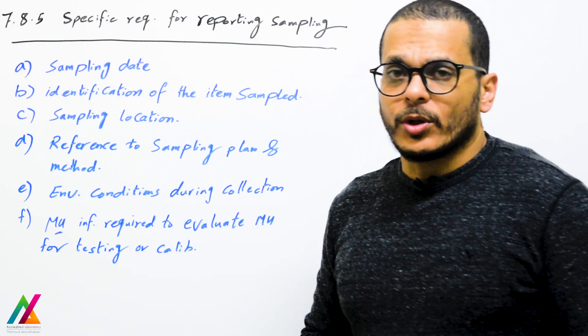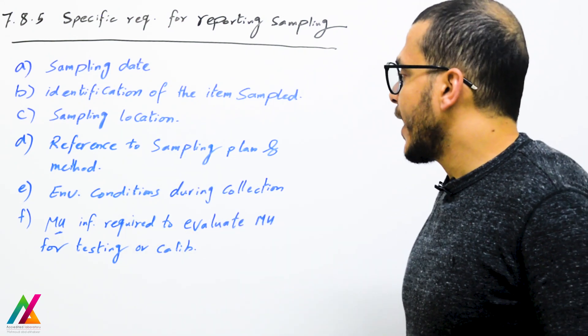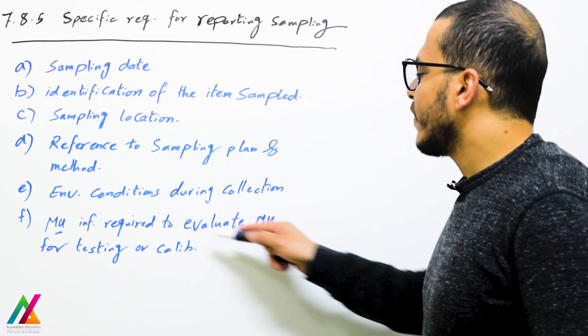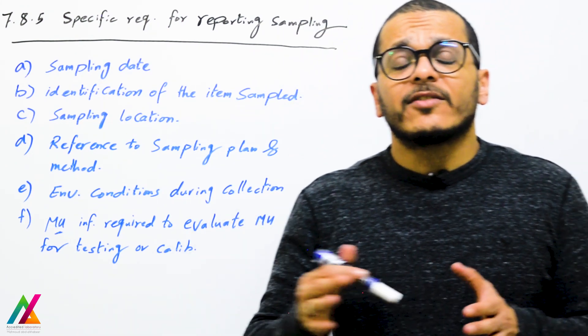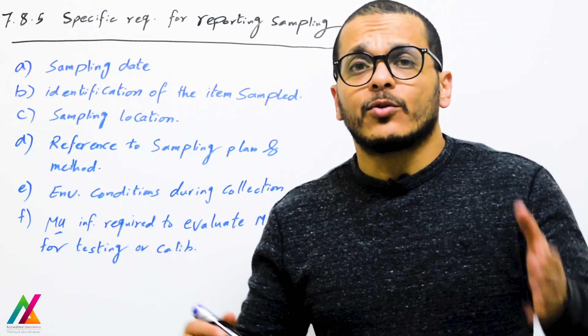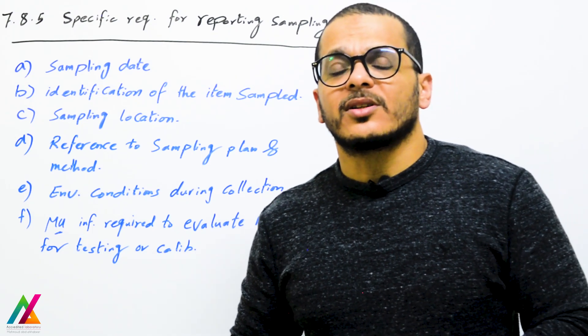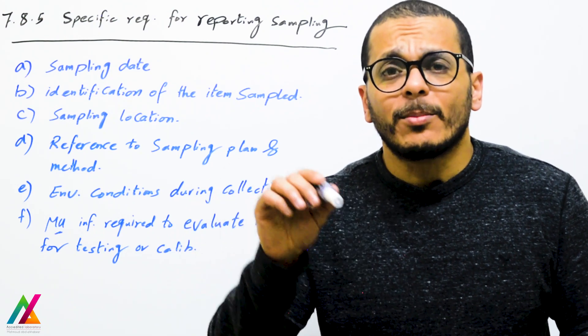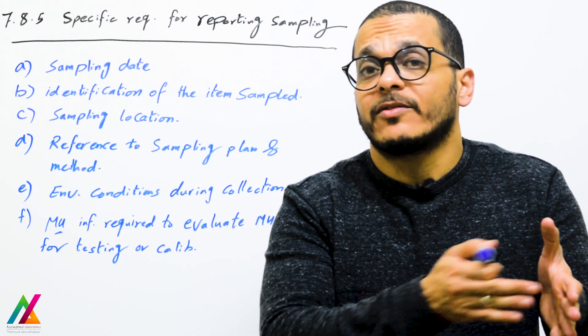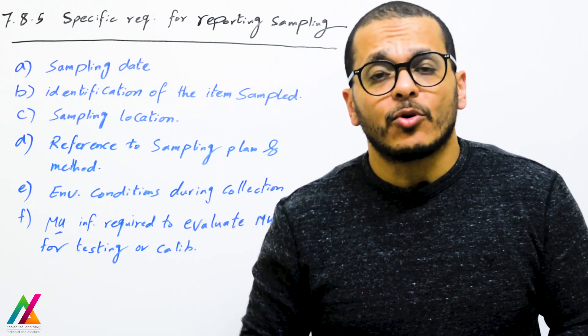If the lab is responsible for sampling, they shall have a report for collection of samples that shall include: sampling date; identification of items sampled; sampling location; reference to sampling plan and sampling method; environmental conditions during collection; and measurement uncertainty information required to evaluate measurement uncertainty. However, you don't need to add the sampling measurement uncertainty value directly to this report — you just quantify it and add it to the combined uncertainty.